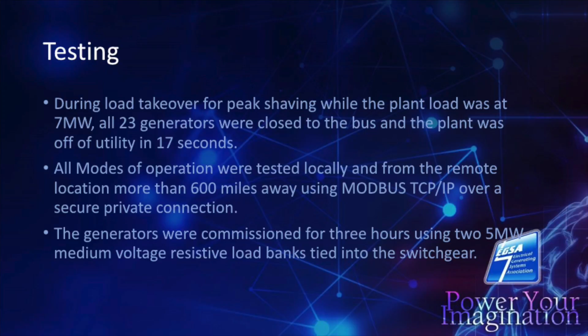Yeah, so basically going into that, we had the cut sheet, and the engineers we had looked at the largest load steps that we could incur while powering the plant. While this is a very state-of-the-art facility, every motor load is on a drive. We still ran into not having enough spinning reserve, so we had to make that change.